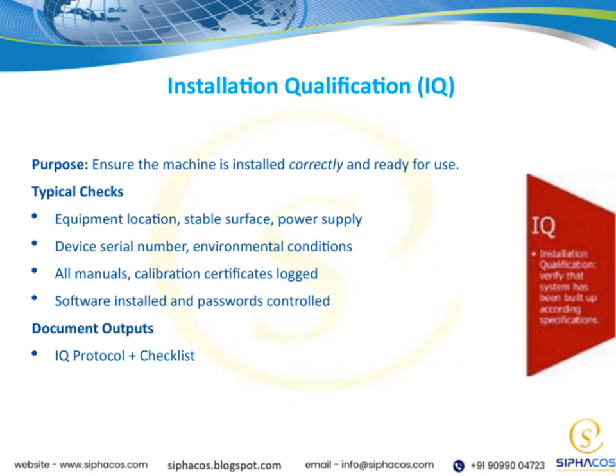Additionally, we need to verify that the software has been installed correctly and that access is controlled through passwords. This helps protect the system from unauthorized access and maintains data integrity. Finally, the documentation outputs from this phase include the IQ protocol and a checklist. These documents serve as a record that all installation steps have been verified and completed properly.